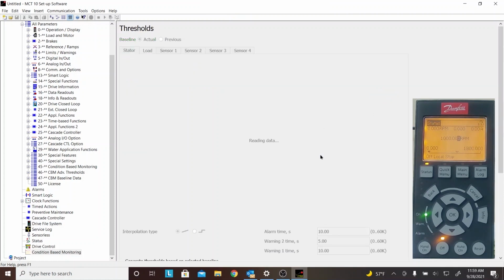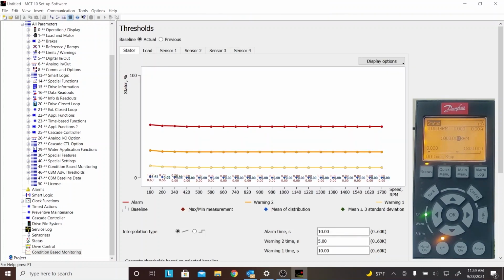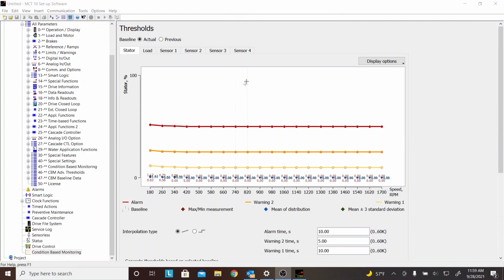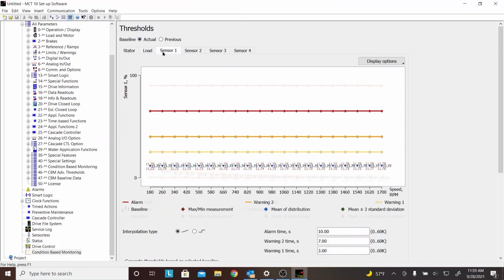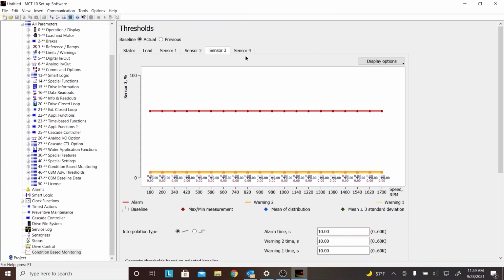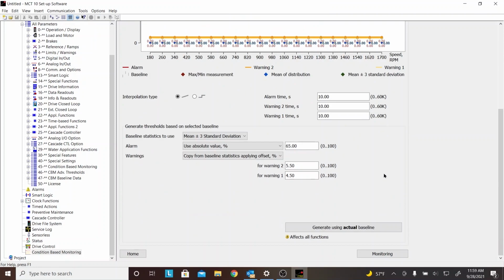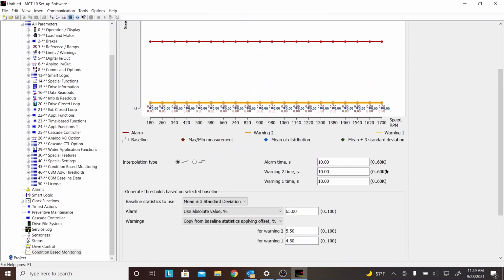So let's move forward. We hit the next button. Now what does the software want us to program? It wants us to program the thresholds. Now I'm going to go ahead and just take this keypad out of here so it doesn't visually interrupt what we're doing. So now we've got to set our limits, which are our thresholds, and we're setting them based on the actual baseline. Again, like we spoke earlier, we have all the envelopes, and all these envelopes have to be set up before we generate the actual values against the baseline. But again, we set all these values up to the manual and the standards they put in the manuals.